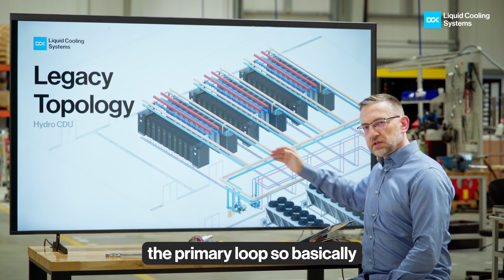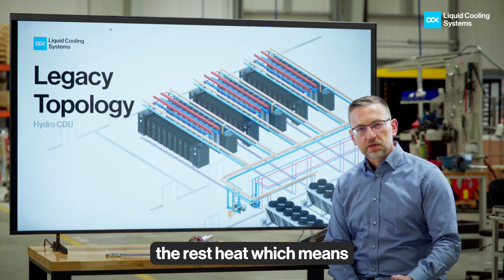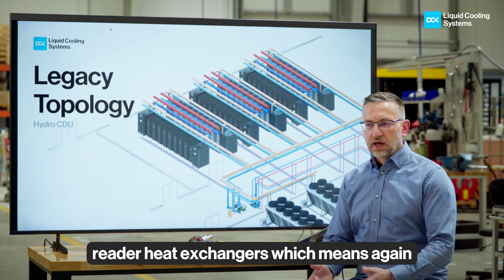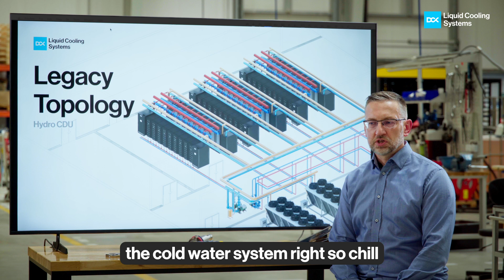First of all, there are 2 problems with that. One is that you need to start fighting for space inside of that server room, because for those CDUs you need to run the primary loop - the facility water system. You also need to run another set of pipes from the CDUs, the technical cooling system. Additionally, if you're thinking about the NVL72, you need to account for rest heat, which means you'll probably have to use rear door heat exchangers - meaning another set of pipes for the coolant, the cold water system, so chilled water to those rear door heat exchangers. So that means you have lots of pipes inside of that one rack group.